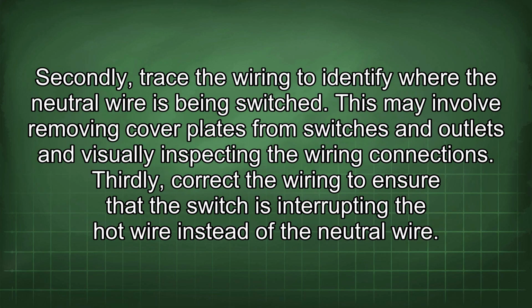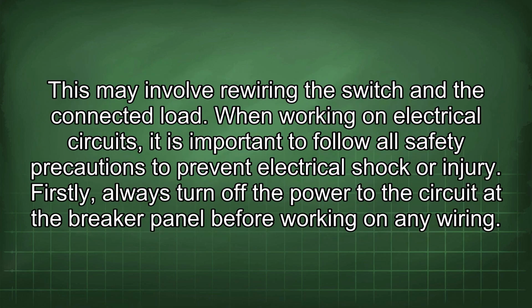Secondly, trace the wiring to identify where the neutral wire is being switched. This may involve removing cover plates from switches and outlets and visually inspecting the wiring connections. Thirdly, correct the wiring to ensure that the switch is interrupting the hot wire instead of the neutral wire. This may involve rewiring the switch and the connected load. When working on electrical circuits, it is important to follow all safety precautions to prevent electrical shock or injury.